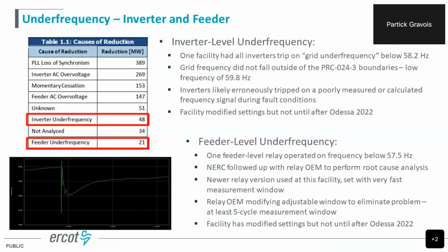The next is under frequency. So this is kind of a big topic as well. There was both inverter level under frequency and feeder level under frequency. For the inverter level, we had one facility that had all their inverters trip on a grid under frequency below 58.2. The lowest grid frequency was actually 59.82. So this, I think, was basically just the wrong settings. So it took a while for them to get this set correctly.